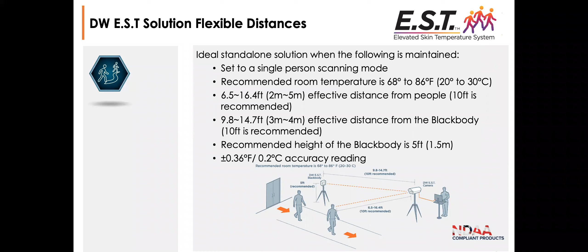Looking at the software itself, the cameras connect directly to the PC. Once installed and the cameras are connected, the software will automatically find the black body in the field of view. That's its reference point, providing a constant reference temperature. At that point, the software does self-calibrating in real time between the black body and the surrounding area.